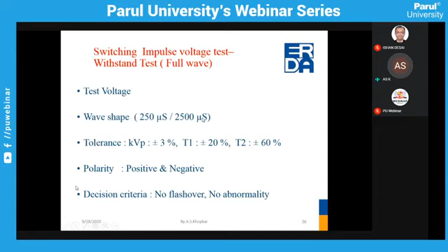So the standard gives different timings for the transformer, not this. Again, here there are three procedures given in case of switching: procedure A, 3 positive, 3 negative; procedure B, 15 positive, 15 negative; and procedure C, 3 positive, 3 negative with additional shots if failure occurs in one shot. Here there is no method D, meaning we don't determine the flashover value, and the standard does not give a way to find out the switching flashover value.